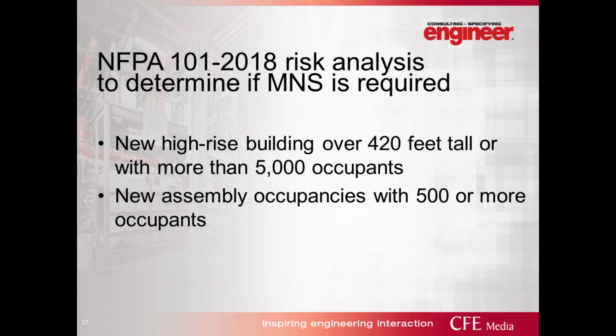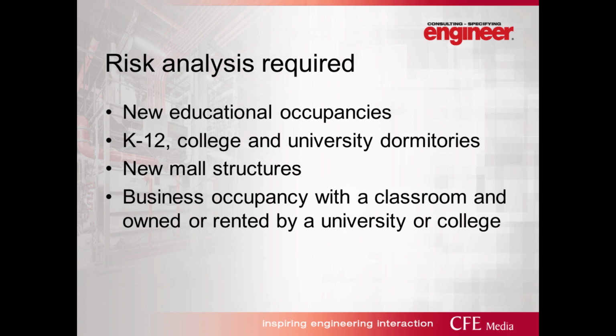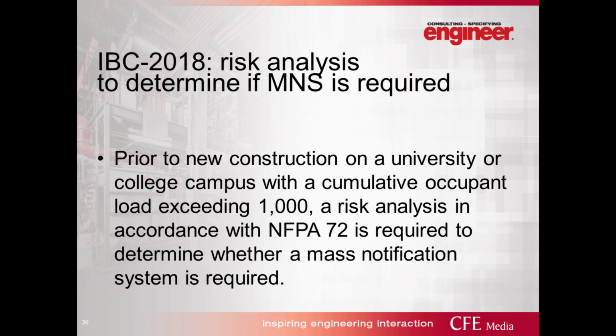Now, there are other requirements that are coming into the codes, into NFPA 101, as well as the IBC. So here are some examples. In the 2018 edition of NFPA 101, there is a requirement that a risk analysis be performed to determine whether a mass notification system is required for new high-rise buildings when over 420 feet, or when there's more than 5,000 occupants in a high-rise building. For new assembly occupancies with 500 or more occupants, a risk analysis is required to determine whether it's required. New educational occupancies, K through 12, college and university dormitories, new mall structures, and business occupancies with a classroom owned or rented by a university or college, okay? So a risk analysis is required under 101 for those types of occupancies.